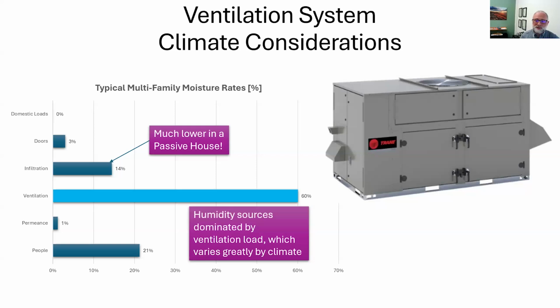We know that passive house buildings have greatly reduced infiltration, so the biggest source of humidity is often the ventilation air. And this is especially an issue in mixed humid and hot humid climates. For this reason, it's often most economical and energy efficient to treat humidity by drying out the incoming ventilation air. The ERV will moderate the humidity, but it's often helpful to provide additional cooling to dry out the air before it's introduced into the building. And this can often eliminate the need for costly and inefficient dehumidifiers inside the building.